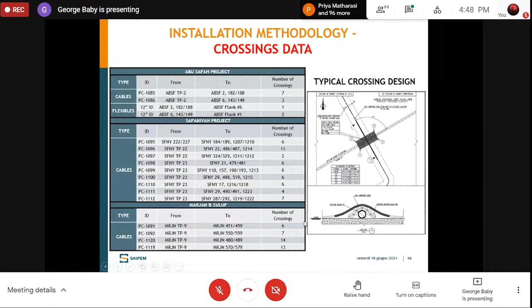When you pull the cable to the platform, it goes through a pipe called a J-tube, and you require some accessories to protect the cable. These are the fittings - this one is called a bend restrictor. It prevents the cable from bending beyond a certain limit, the minimum bending radius, protecting the cable from damage.